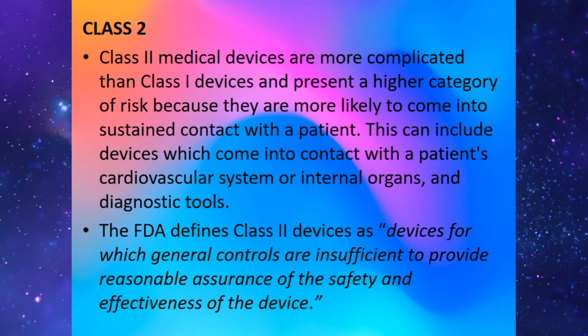Class 2 products pose only moderate risk and are declared via 510(k) declarations. Class 3 products are at high risk and they need pre-market approval by applying to regulatory agencies.